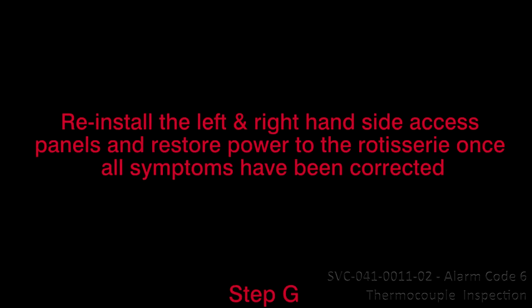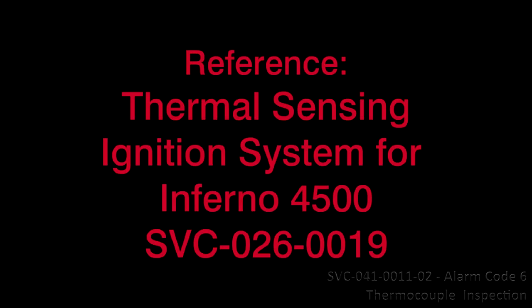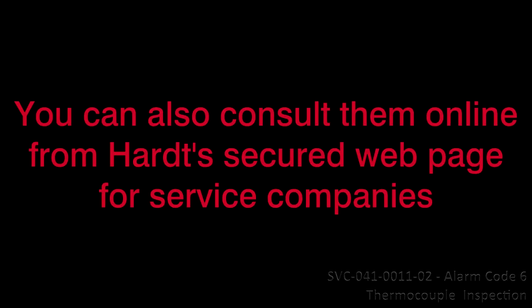8. Reinstall the left and right-hand side access panels and restore power to the rotisserie once all symptoms are corrected. This concludes Video Service Guide Resolution 5, Inspection for Alarm Code 6, Thermocouple, SVC-041-0011. Reference Thermal Sensing Ignition System Service Guide SVC-026-0010 for Inferno 3500 and GC, or SVC-026-0019 for Inferno 4500. Contact Hardt if you require these references. You can also consult them online from Hardt's secured webpage for service companies.